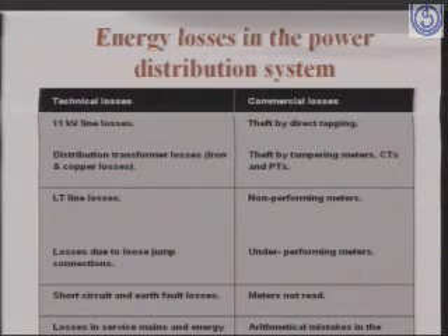When we segregate these losses, where do they occur? Technical losses can fall in such categories. On the left side you can see there are 11 kV line losses, distribution transformer losses, and when we talk about distribution transformer losses, there are iron losses and copper losses. Then LT line losses, then losses due to loose jumper connections, then short circuit and earth fault losses, then losses in the service mains and energy meters. They are the technical losses.